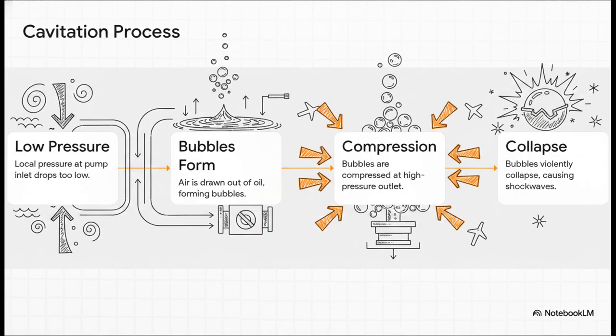Let's do a step-by-step breakdown of how a microscopic physical anomaly turns into a literal chain reaction of destruction known as cavitation. Remember, the pump doesn't actually draw the oil in, atmospheric pressure delivers it. So step 1, the local pressure on the inlet side of the pump drops way too low. Because of this, step 2: air is literally drawn straight out of the oil itself, forming bubbles.